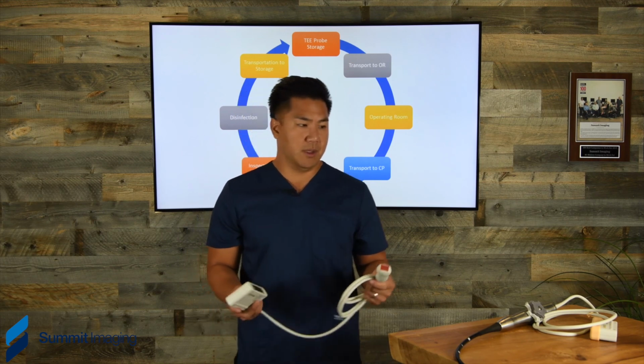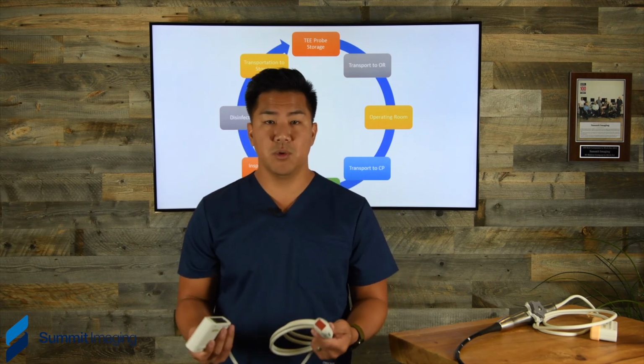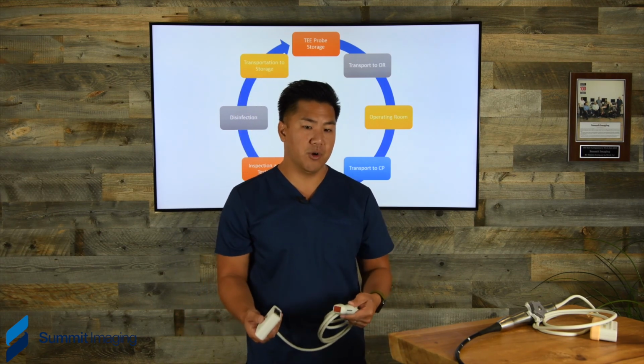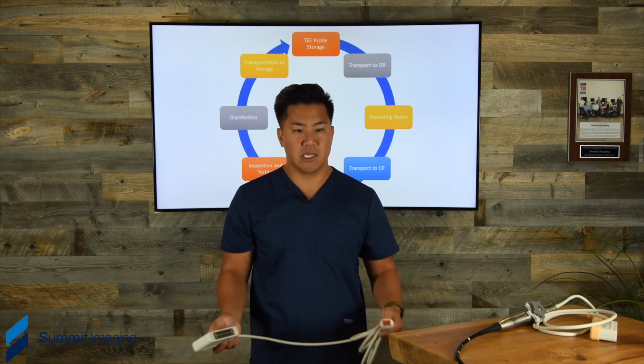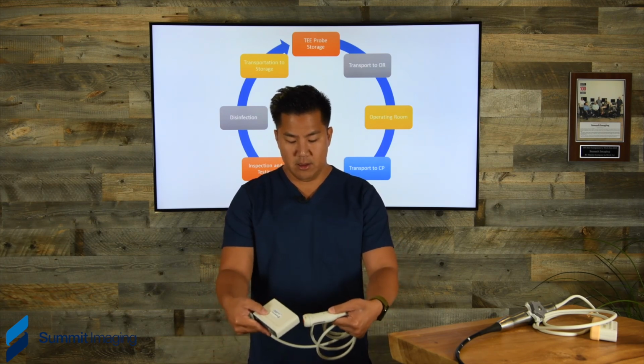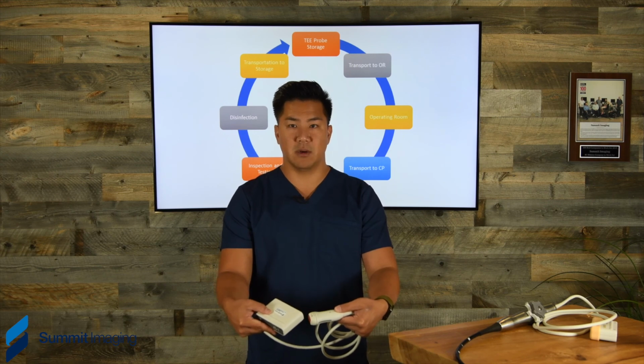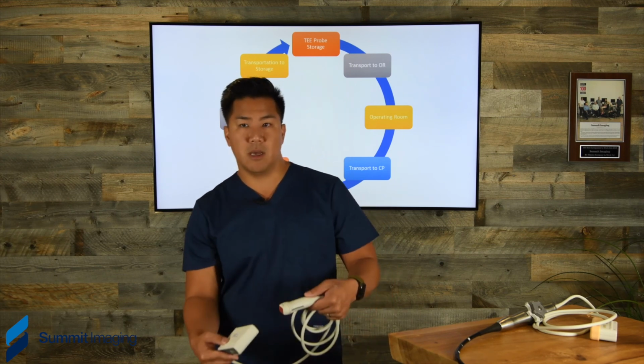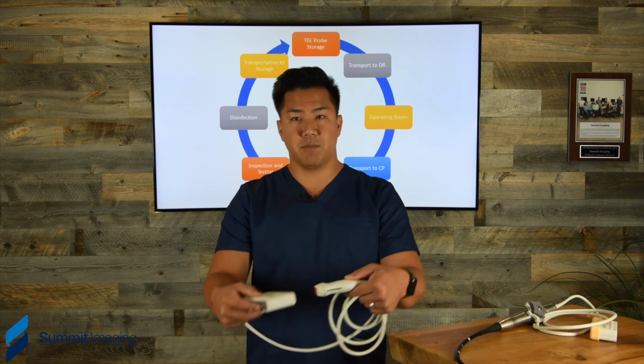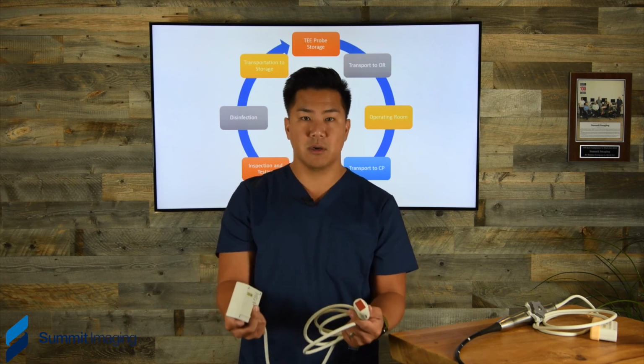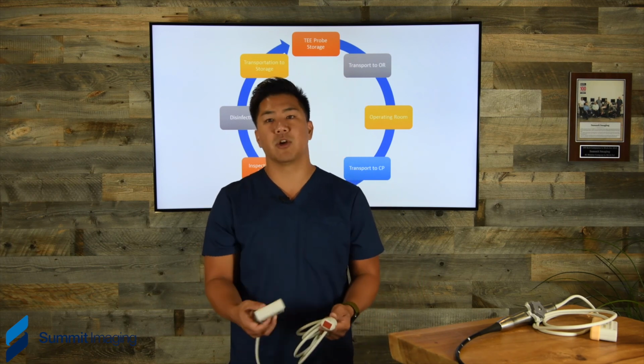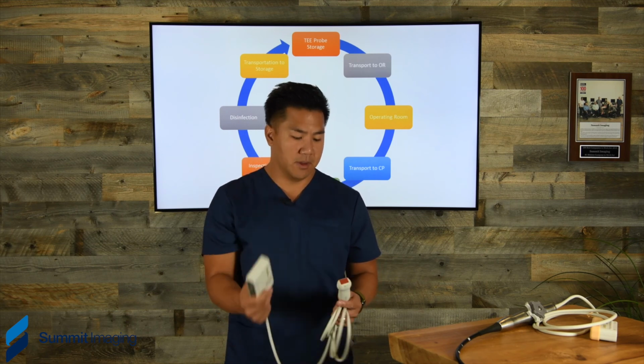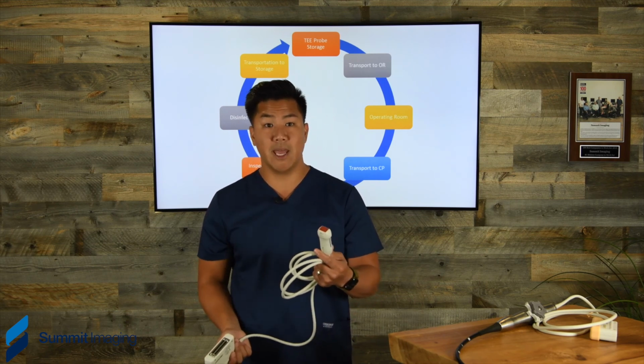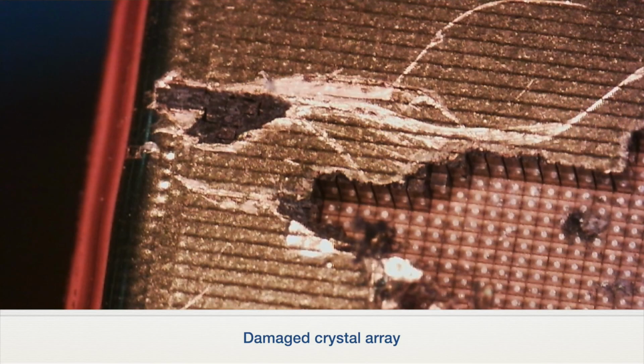And the issue, sometimes, when we see totes being used with TEE probes and standard probes, is that they go into a box and then the crystal is next to the connector. And as people walk down the hall, the crystal starts banging onto the connector and therefore damaging that crystal, because this connector is full metal and this just has a rubber lens covering a ceramic crystal that's very fragile. So be careful as you're transporting them.